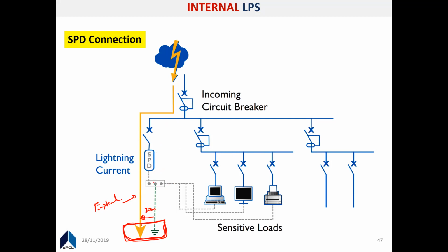But the earth termination is also important there. If you are connecting it incorrectly, it will pose a lot of problems, because sometimes people connect this earth at a different end, causing unnecessary problems to the installation. So these are the earthing and bonding concepts. It's beyond LPS, beyond the basics of BS7671, but you have to keep in mind that earthing and bonding should also be considered.